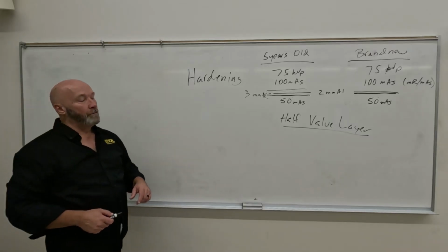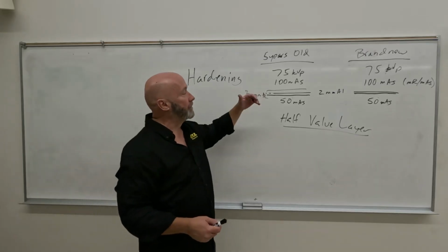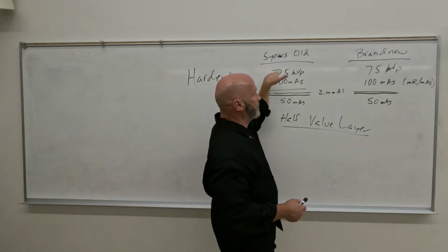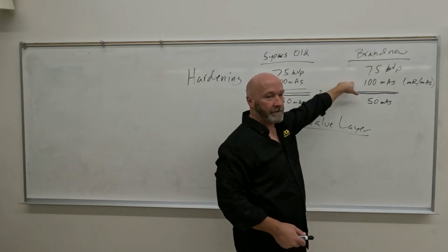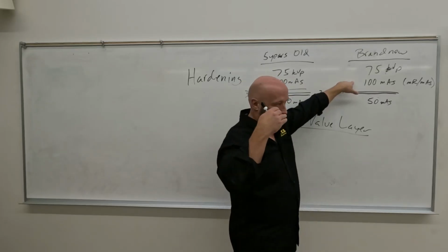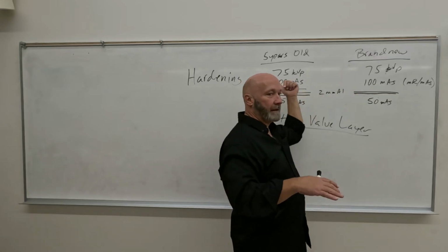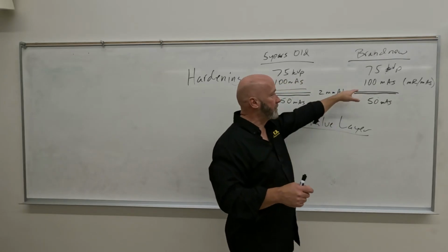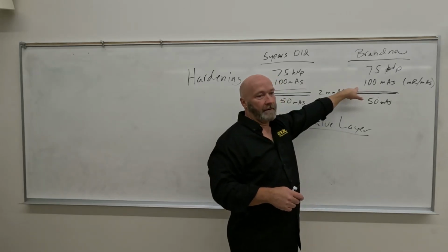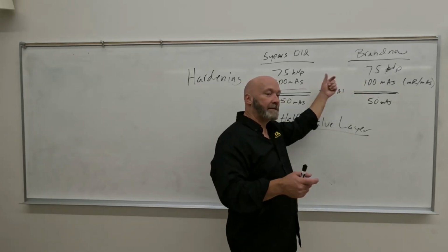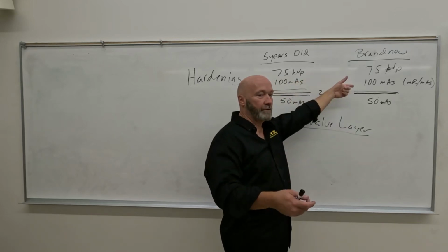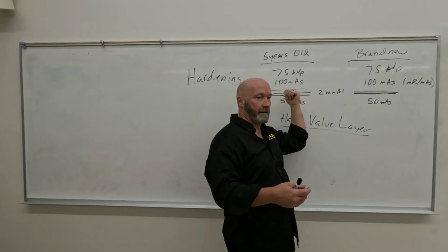Where does the tanning come in? Like, it makes a layer that's not filtering it? Yeah, it is filtering it. So the tanning comes in, this tube shot like that 5 years ago. But at year 1, you had some degree of tanning. So they had to go in and adjust the technique because it wasn't putting out 100 mAs anymore. It was maybe putting out 90 mAs. So they adjusted it so it still put out 100 mAs. And then in year 2, they had to do it again because it was, again, putting out 90.